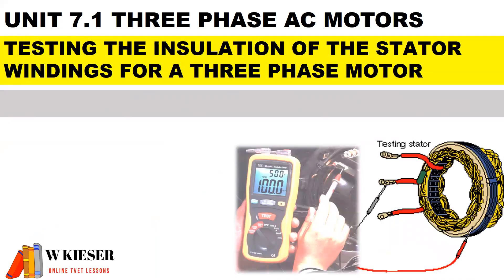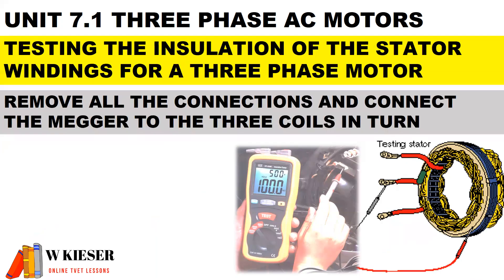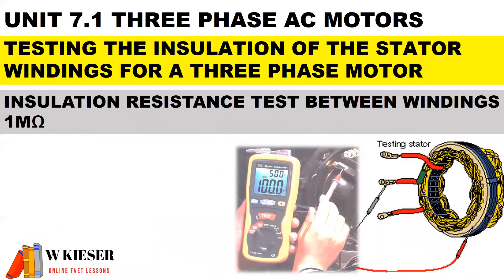In this final section, how do we go about testing the insulation of the stator windings for a three-phase motor? We use an insulation resistance tester, also known as a MEGA. We usually set it to about 500 volts DC and then hit the test button. First, we remove all the connections and connect the MEGA to the three coils in turn. For an insulation resistance test between windings, we should get a good reading of one mega ohm. For an insulation resistance test to earth, it also requires a reading of at least one mega ohm.